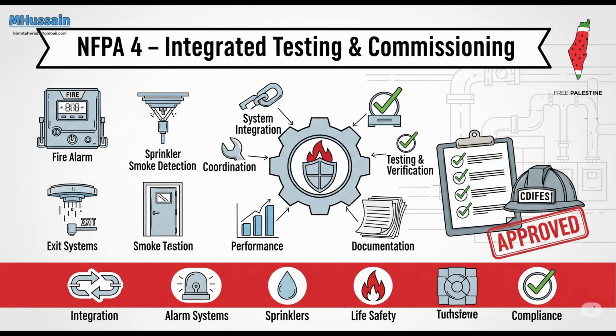Okay, so what doesn't it cover then? Is it replacing other tests? No, and that's crucial. NFPA 4 does not cover the testing of the individual systems themselves. Those requirements are still handled by other specific standards, like NFPA 72 for fire alarms, or just the manufacturer's own instructions. So NFPA 4 picks up where those leave off. Precisely. It ensures the system of systems works in concert.